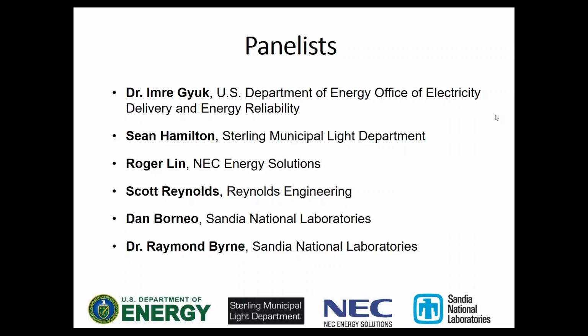So we determined the end of life as 10 years, and we asked each of the vendors to do their own degradation calculations to determine beginning of life capacity needed to meet what we were looking for at end of life after 10 years. We had to give them assumptions on how this was going to be used and cycled, because if you cycle it differently, you get different degradation results. So to make a level playing field, we gave them assumptions about usage and told them we wanted 3 megawatt-hours at end of life, after 10 years.